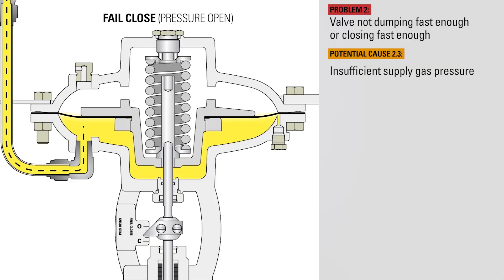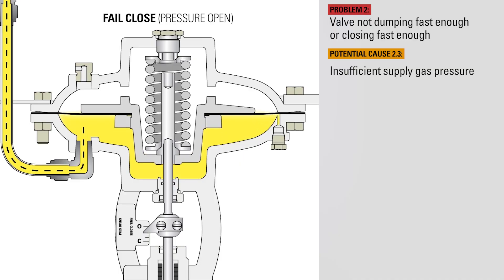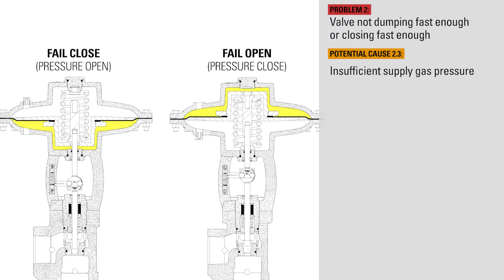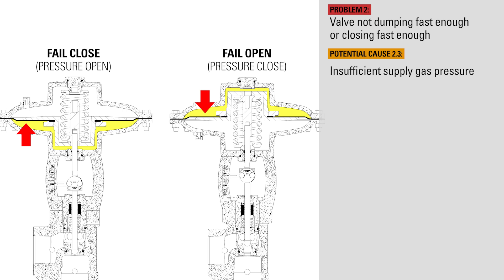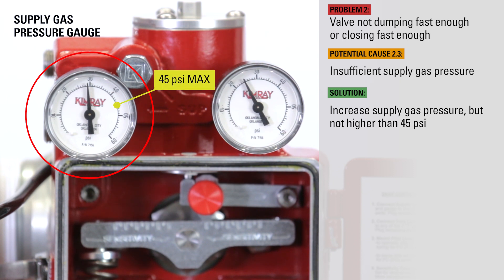If the pressure of the supply gas is too low, it may not be able to create sufficient force in the actuator to open the valve fully in a fail closed valve, or to close the valve fully in a fail open valve. Try increasing the supply gas pressure to see if that fixes the issue. Make sure not to adjust the pressure higher than 45 psi, which is the maximum allowable for the Gen 3 pilot. Pressures above that could potentially rupture the diaphragms inside the pilot.